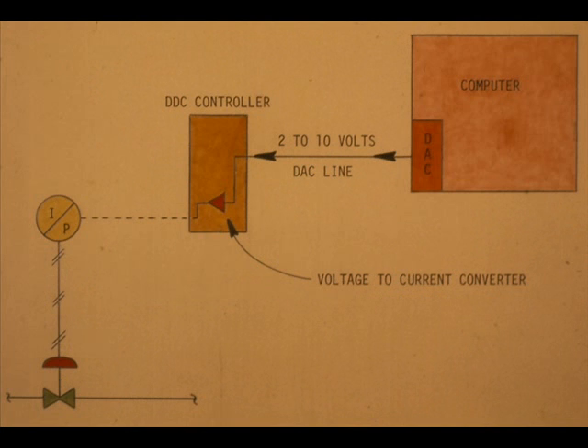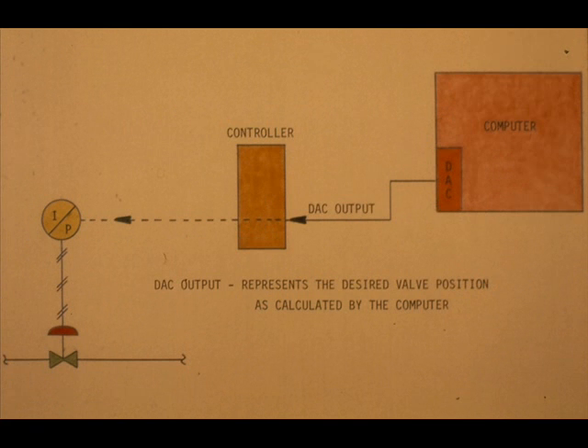A DDC controller receives the DAC signal from the computer and converts the DAC voltage to a proportional output current. The DAC signal, or computer output, represents the valve position the computer has calculated as being optimum for maintaining the desired process value.